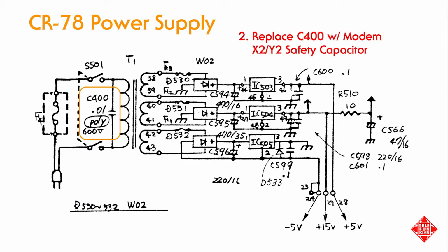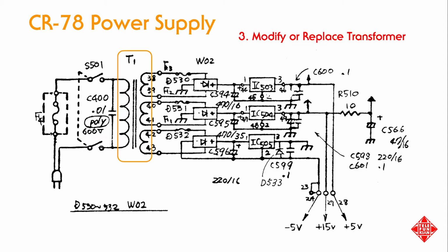We'll also be replacing C400 with a more modern X2Y2 safety-rated capacitor. Safety capacitors are manufactured in such a way that they're guaranteed not to fail short, unlike the capacitor that's currently in the instrument, which does indeed have the potential to fail short, hence the name death capacitor. We'll also need to either modify or replace the power transformer. We'll talk about that more in a minute.